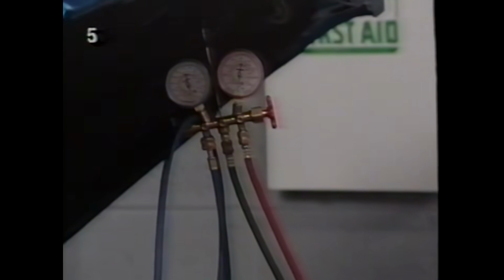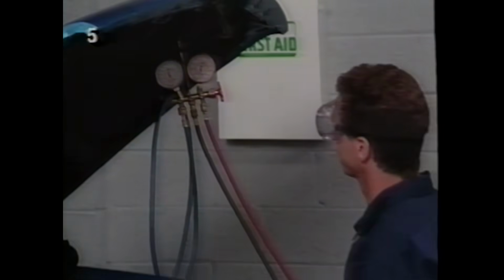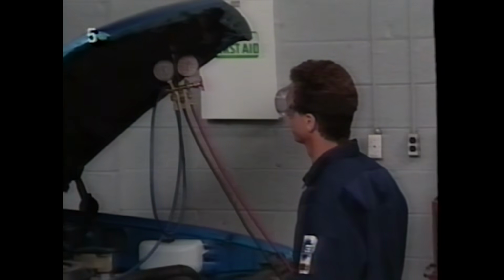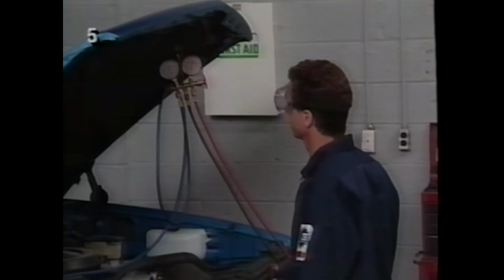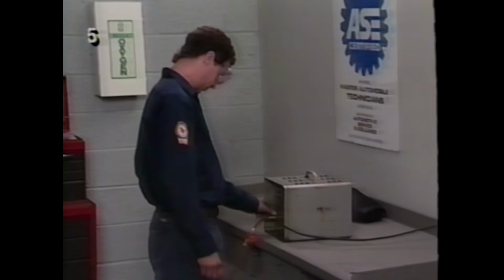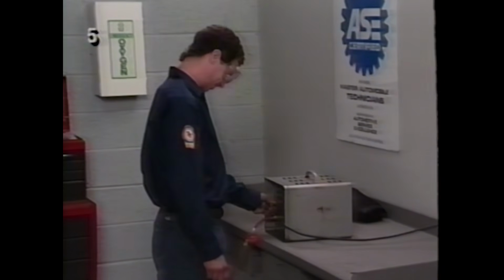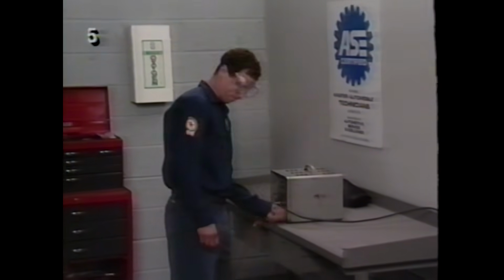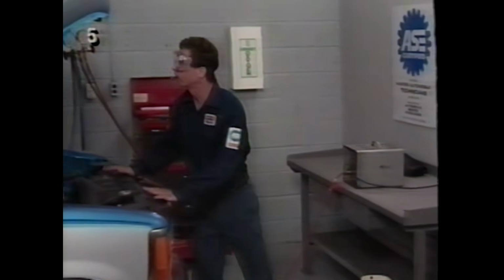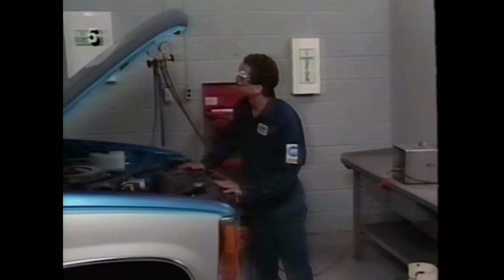The system is completely cleared out when the low pressure gauge reads close to 30 inches of mercury. Some technicians prefer to leave the vacuum attached for several minutes at this point, just for good measure. It's not a bad idea. Turn off the vacuum pump and watch the low pressure gauge for about 5 minutes to see if the system holds vacuum. This is a good way to check for leaks.